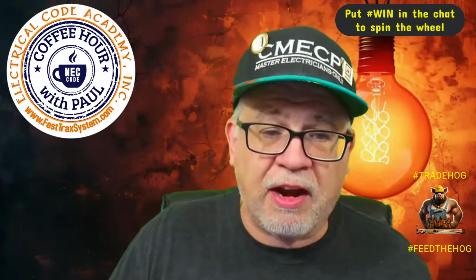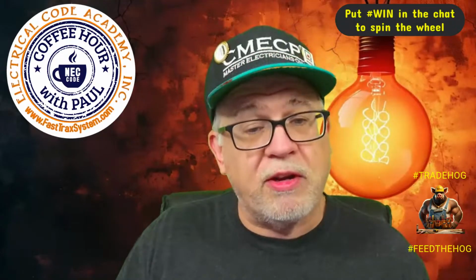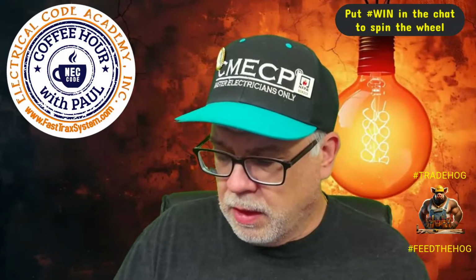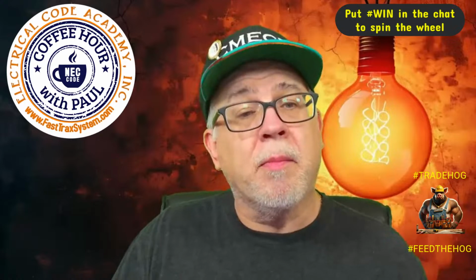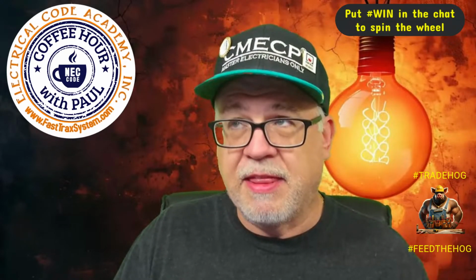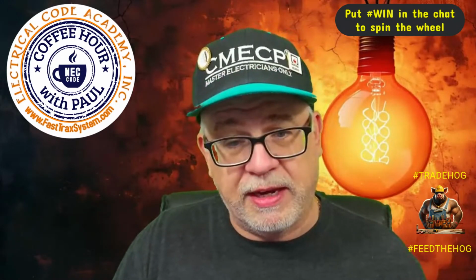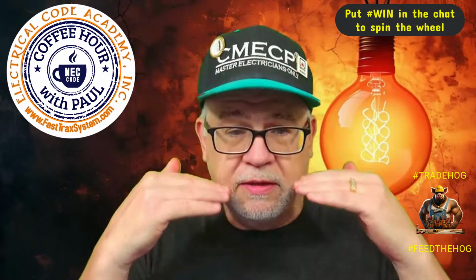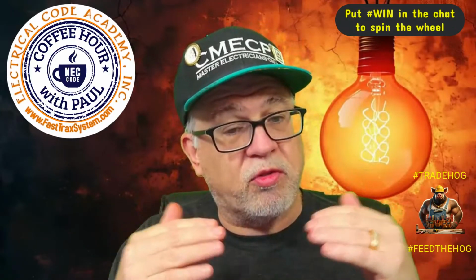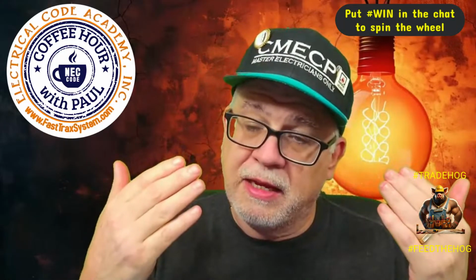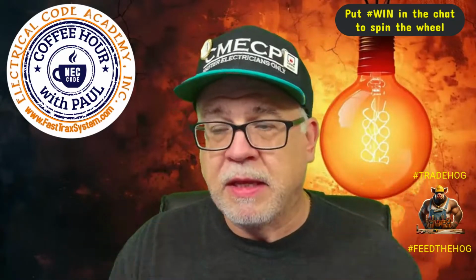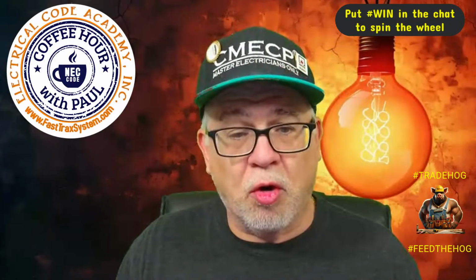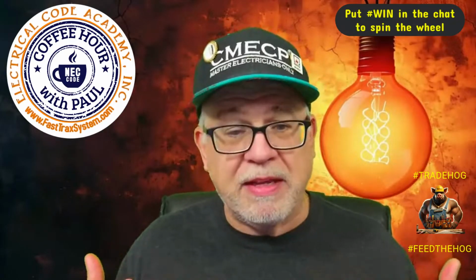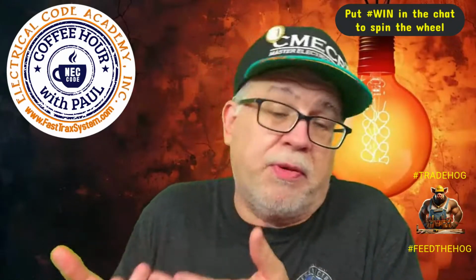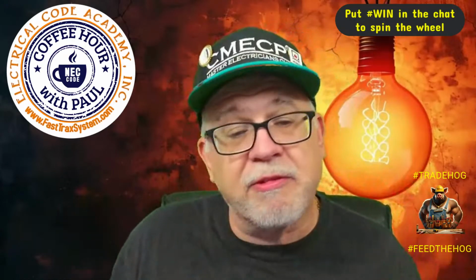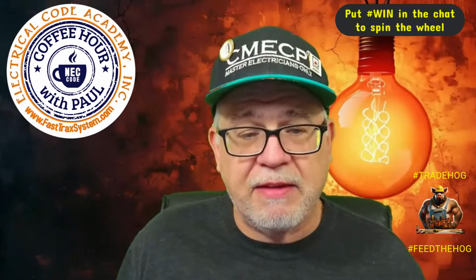Once you start having higher than 5 milliamps, we start questioning whether or not it's really GFCI — in other words, is it meeting personnel safety? That's the whole reason for the whole thing. That's why you have the exception for HVAC, which when it expires will require GFCI. Then they have to go to Class C, which is a much higher milliamp rating than normal Class A. I don't know whether it meets safety, but they must have researched it since they put it in the code, so I guess it does. I never dug deep into it, but they are going to give you more options.